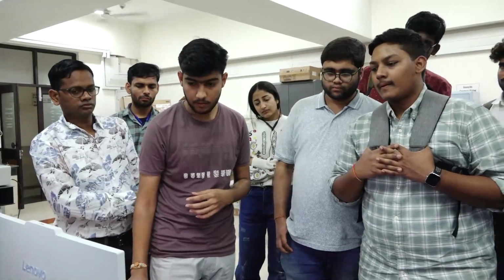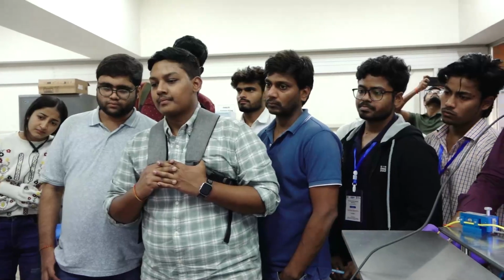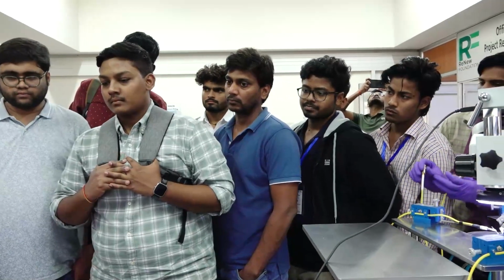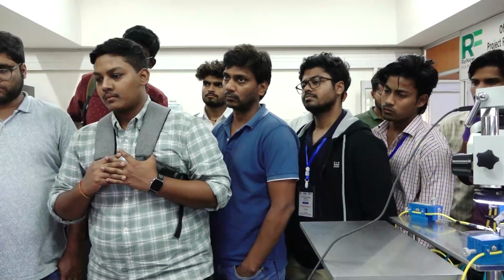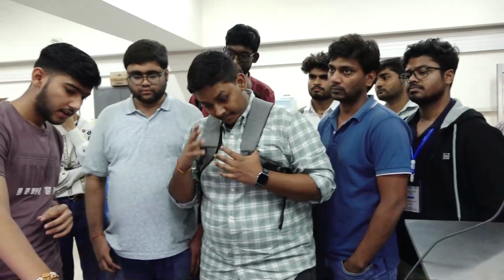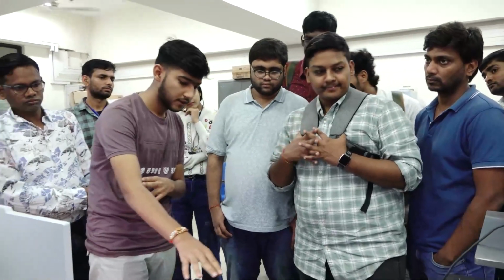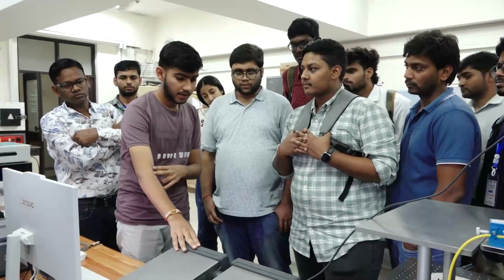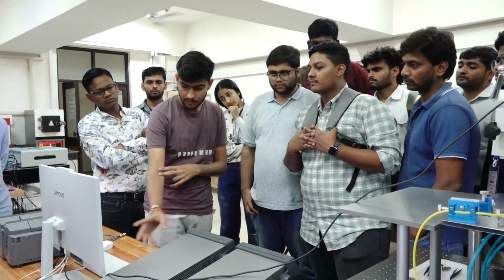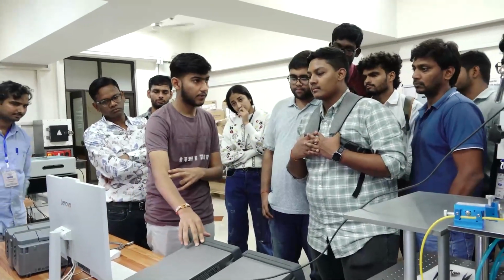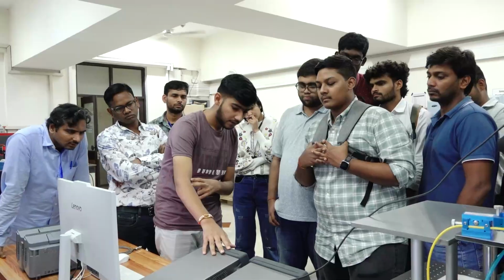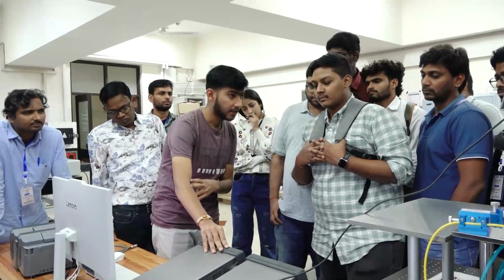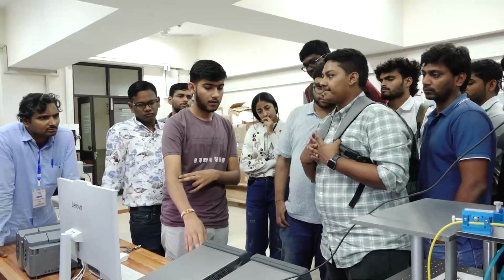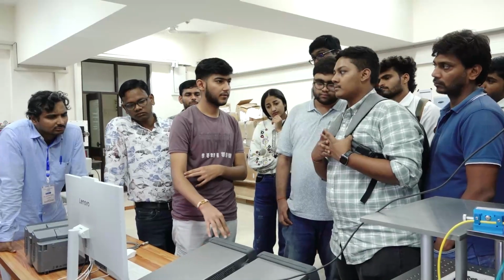Then you will open the Keysight connection expert software to verify if all the SMUs are connected in the order that you have defined. At the time when you are initializing the SMU, you have to give a GPIB ID, which has already been provided. For the master we have given 22, and for the slave we have given 24. It is given physically. When it is moved, you can change it. If you want to know how to change that, then you can read the manual. It is a different process.